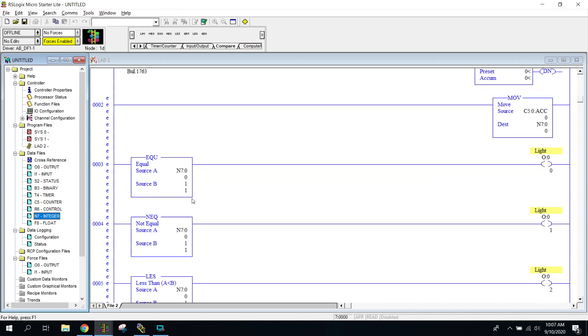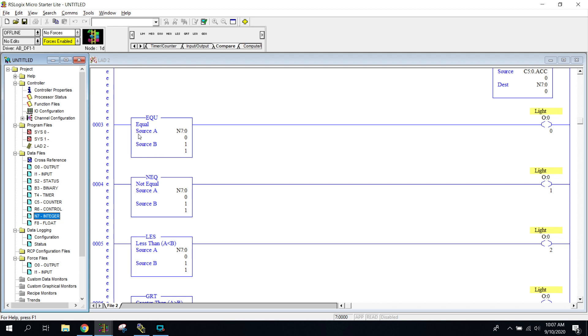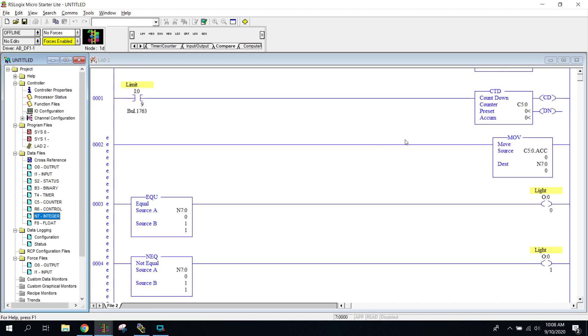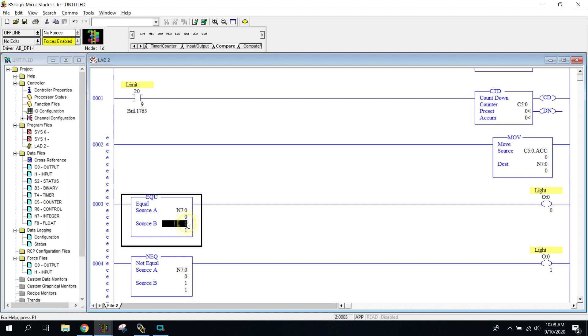I've put a value of one in all of these. The compare is going to take source A and compare it to source B. You could hook a counter up to source B, hook multiple counters, or manually enter a number. We can even change it as we go — look, I just changed it to a four. We could hook it to an N7 with more moves, or even to an analog input, which would give a range of numbers depending on the type of analog input.